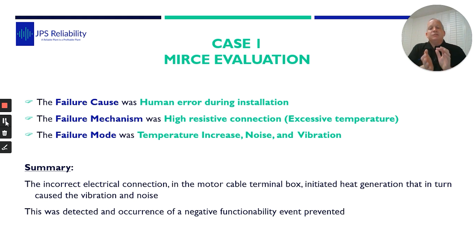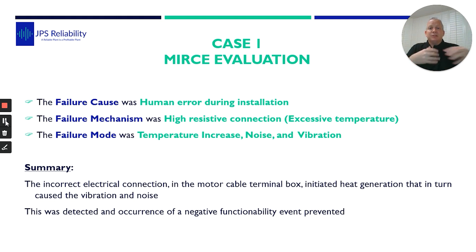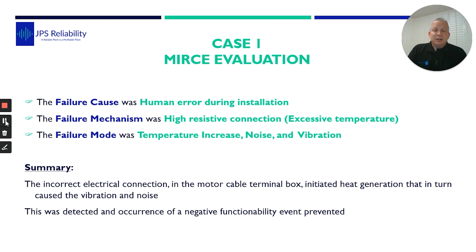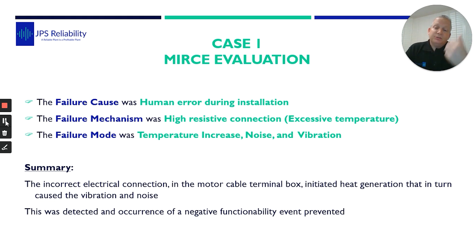Now, this was detected — an occurrence of a negative functionality event was prevented. That means it didn't stop mid-production and cause a big backlog. It wasn't a negative event. So with this knowledge of condition monitoring, we've highlighted why the issue occurred, so we can look at ensuring that people follow procedures. And also on the side of this mode, it'll be a double-check on connections. But it managed this company to put a quick plan in place to mitigate stopping production, to manage that shutdown, to change the motor out — because they knew they had to change the terminal box and just change the motor.